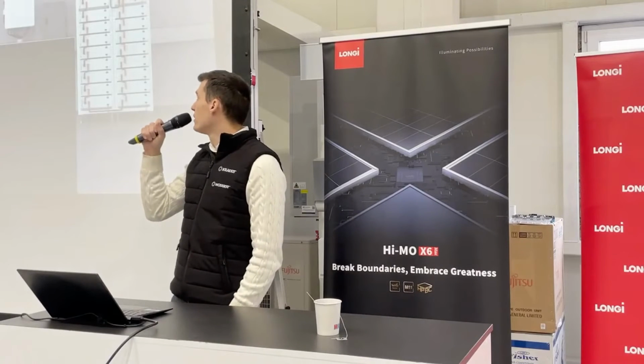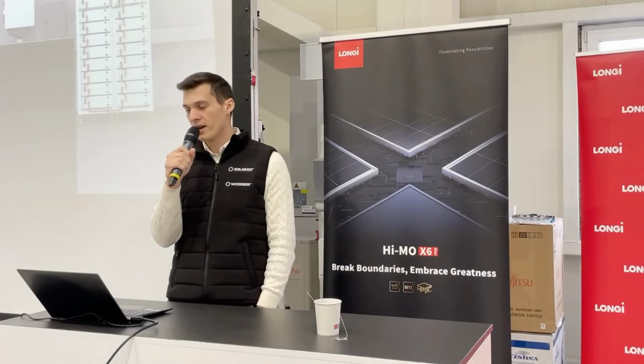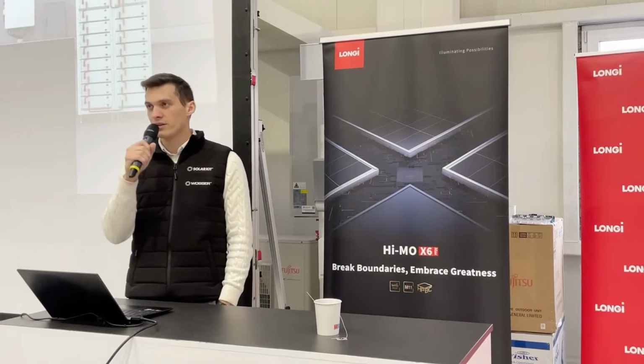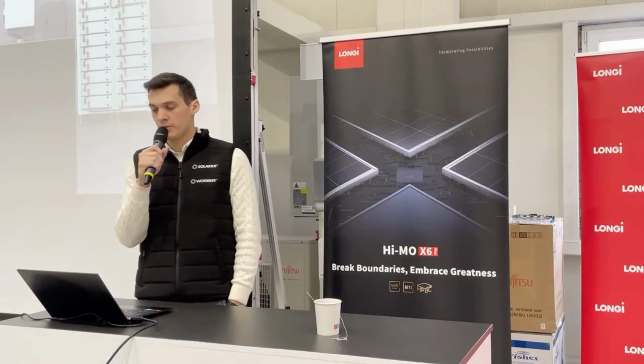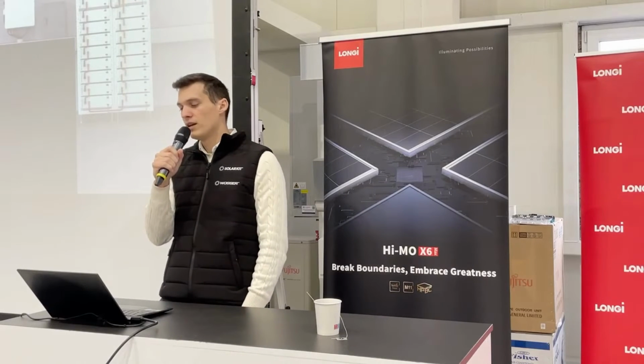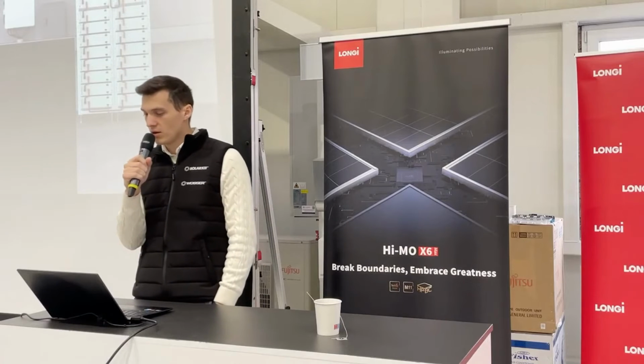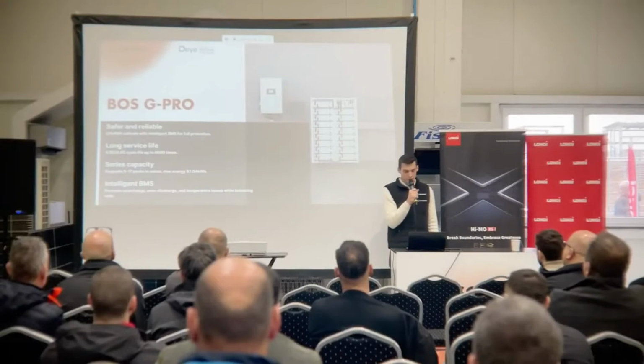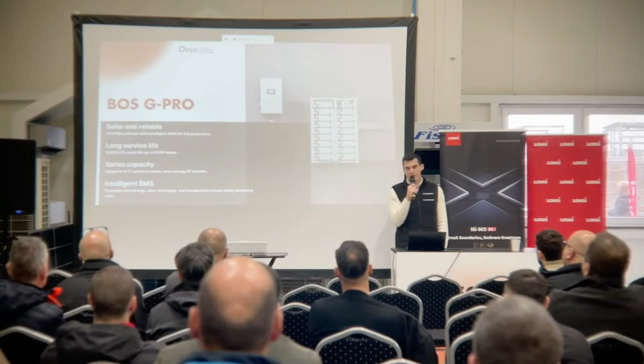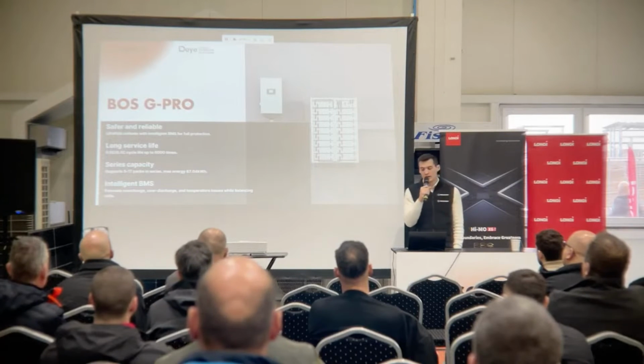So we have the Boss G batteries as well. These are similar in capacity to the Pro B, 5.1 kilowatt hour, and this is the most common one. These are high voltage batteries, so you need to install a BMS for that as well, sometimes called a control box. Basically, it's responsible for connecting the batteries to the inverter, and it will regulate the batteries.